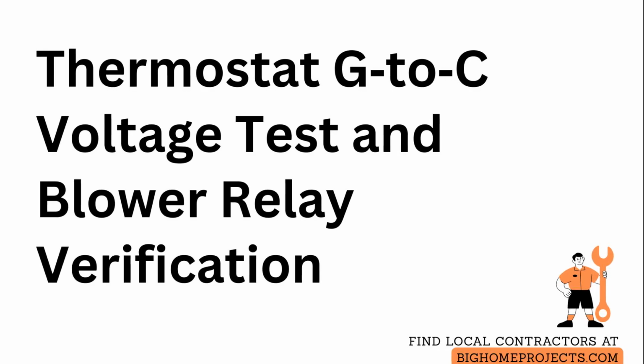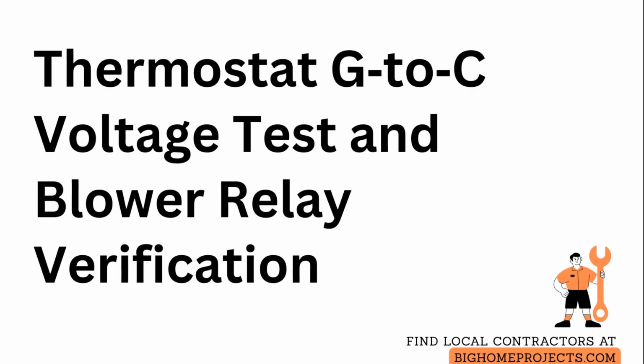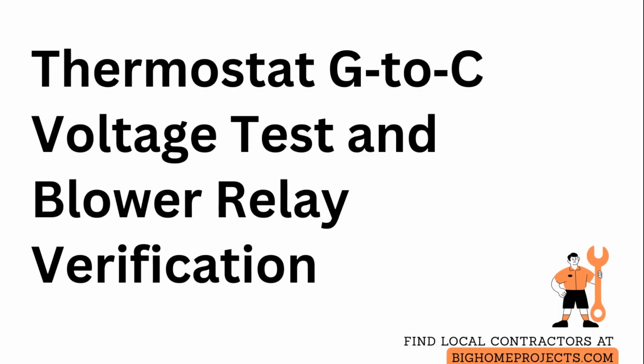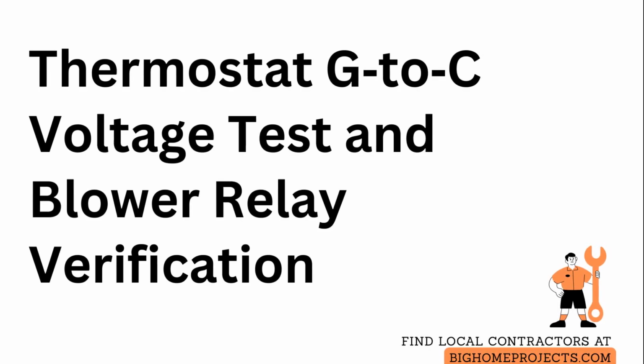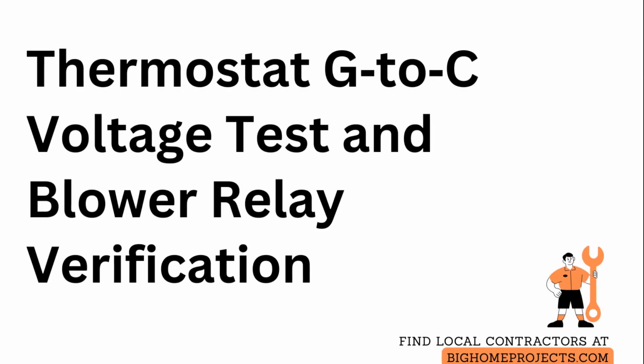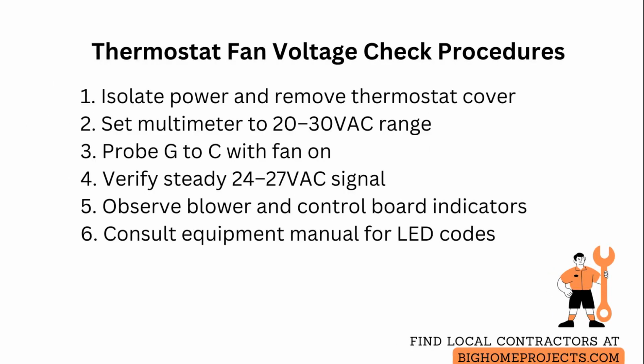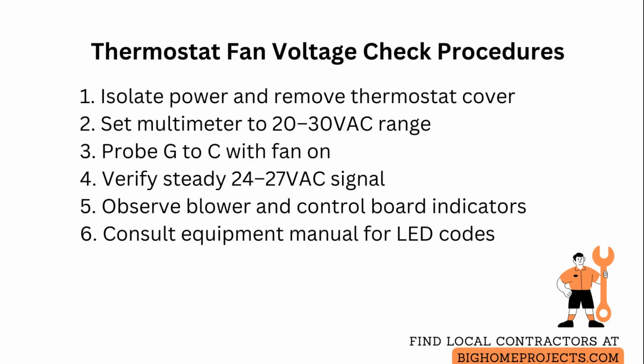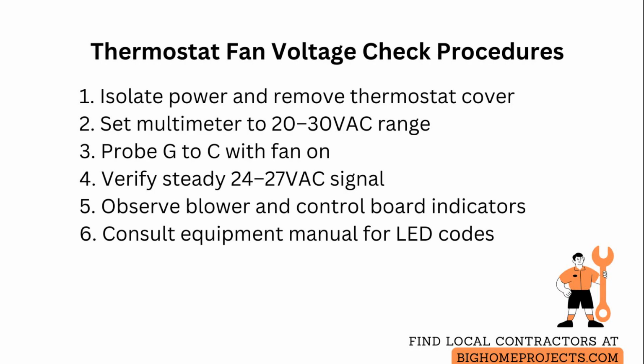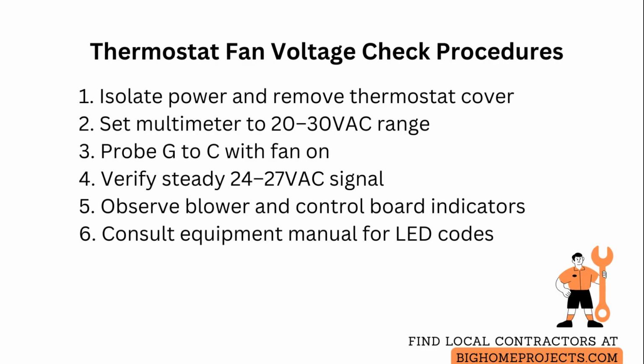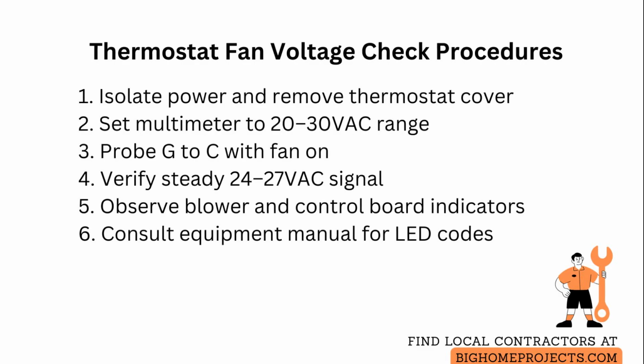When the thermostat fan is turned on and voltage measured between G and C reads 24 to 27 volts, that confirms the thermostat is commanding the blower and the control board is responding. First, isolate power and remove the thermostat cover to access the G terminal and the common C terminal.